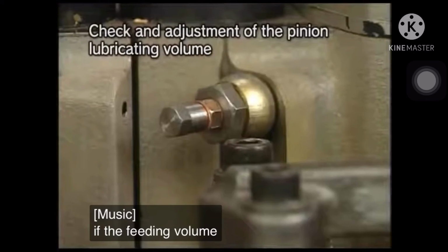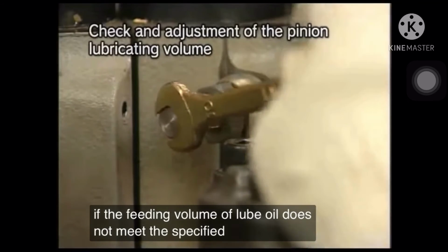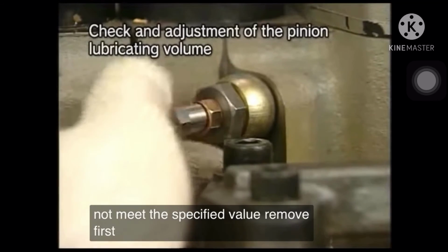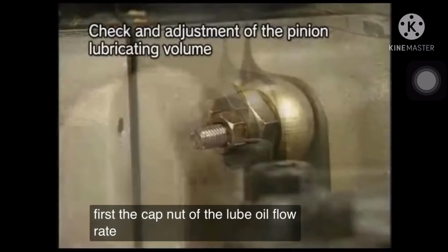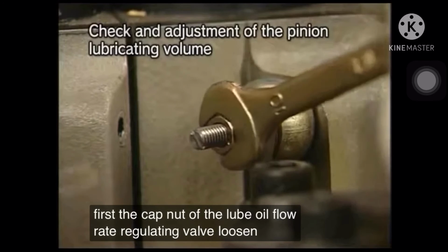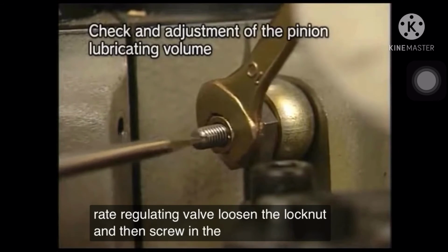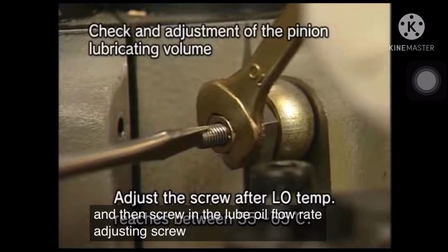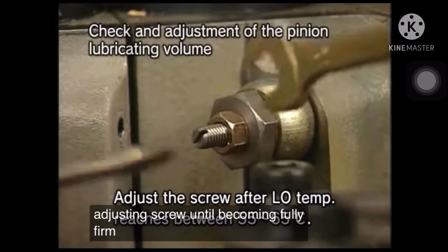If the feeding volume of lube oil does not meet the specified value, remove first the cap nut of the lube oil flow rate regulating valve, loosen the lock nut, and then screw in the lube oil flow rate adjusting screw until becoming fully firm.